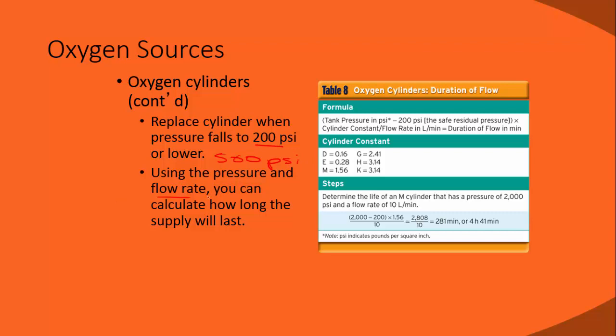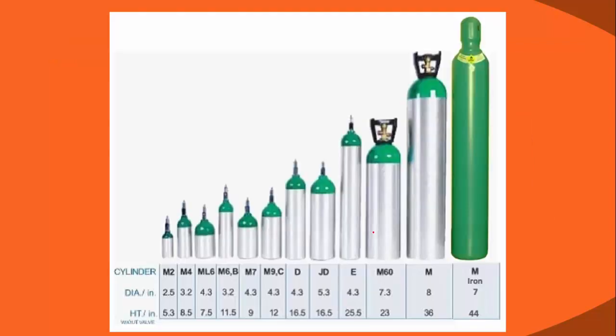Using the pressure and flow rate and a constant, which is here for the cylinder type, we can determine the length of time you can use this tank based on how full it is and what flow rate you're giving, so that it tells us when we're going to have to change out again. So please do be aware of this. I would recommend when you're at your service or on your internship, why don't you just calculate this once or twice just so you have it down based on the cylinder that you're using.